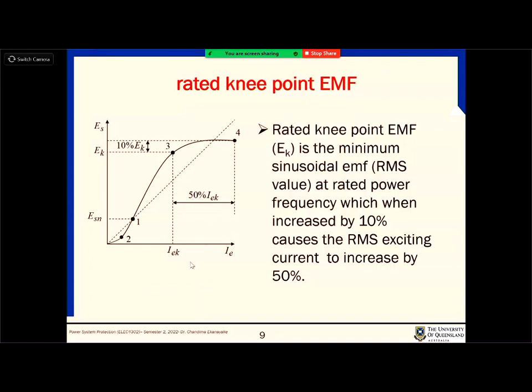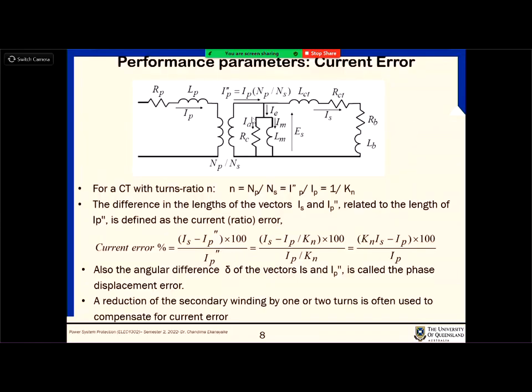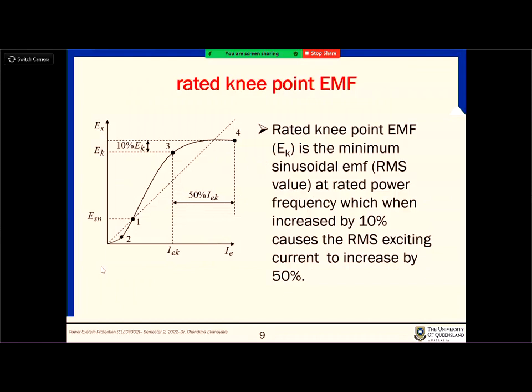So when we are looking at the CTs, it's quite important to look at their characteristics as well, how they change the voltage and what is the relationship between the secondary and primary, right? And for that, here the term IE stands for the excitation current. If you look at the previous one, this is that current, right? That's the magnetization current. It's like the B-H curve when you're looking at transformers, where you see the magnetic flux, and then on the horizontal axis you see the magnetization current. So that is the same thing, right?